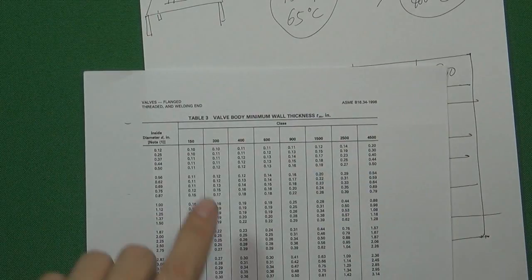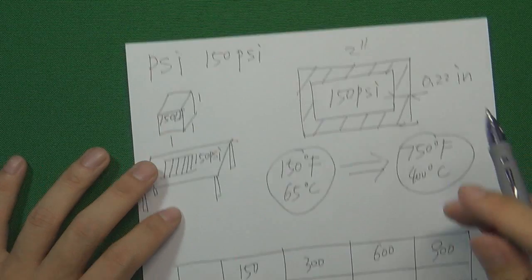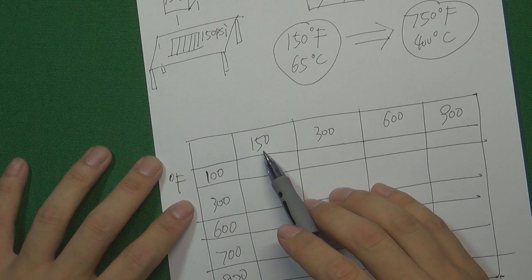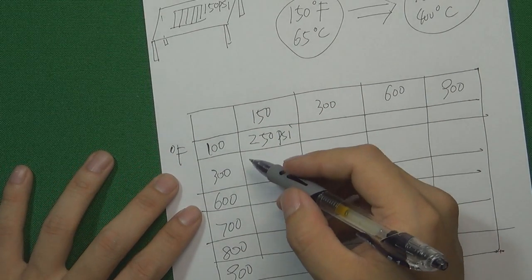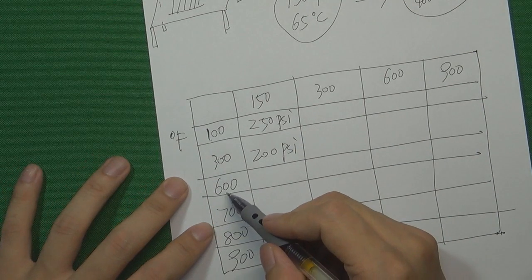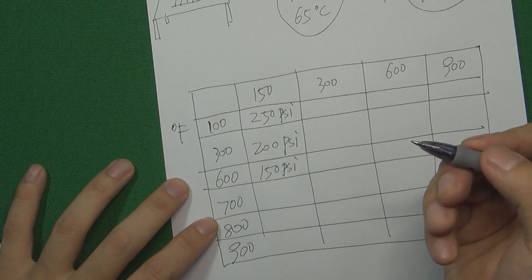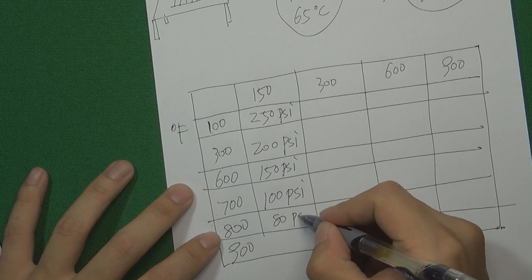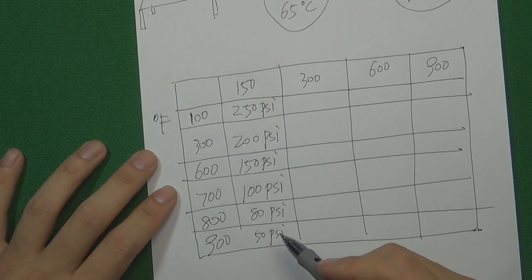For example, using the wall thickness table we designed a 2-inch valve with 0.22-inch wall thickness. In this temperature-pressure rating table, at 100°F, the valve may be able to hold around 250 psi — more than 150, because the temperature is low. At 300°F, it can hold maybe 200 psi. At 600°F, maybe just 150 psi. At 700°F, maybe just 100 psi. At 800°F, maybe 80 psi. At 900°F, maybe just 50 psi. So we call this the pressure-temperature rating table.